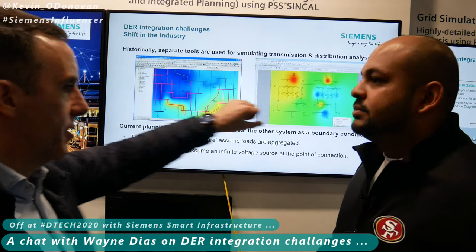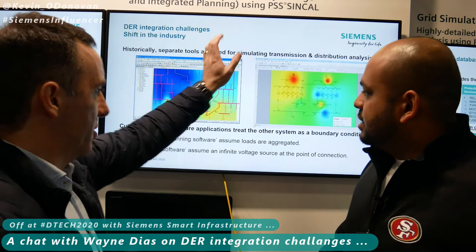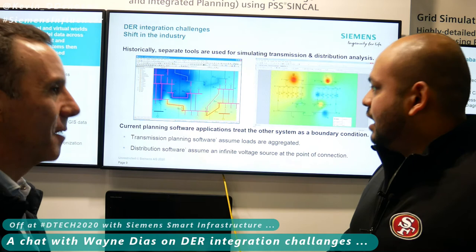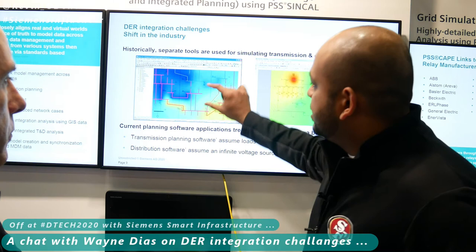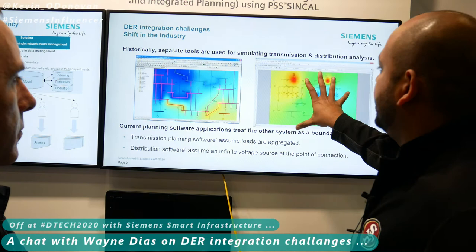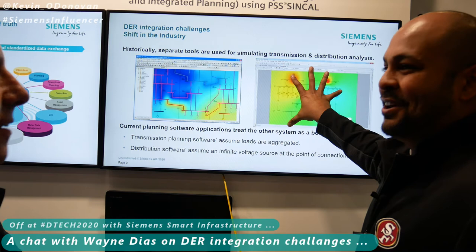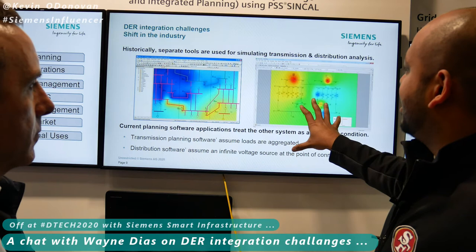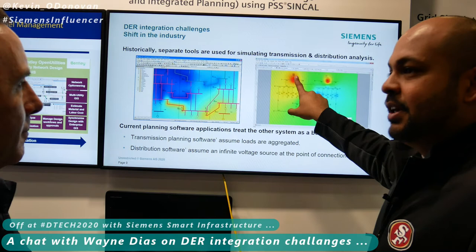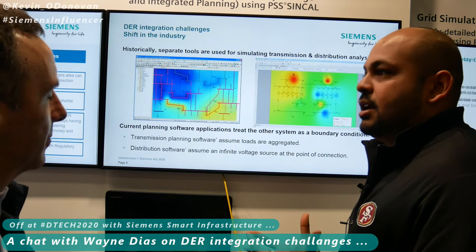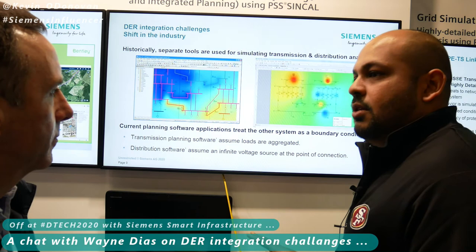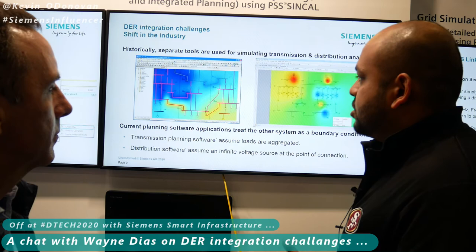What we were chatting about earlier in the week is that there are assumptions made in the models — balanced system, unbalanced system. Currently, TSOs run their analysis by considering the entire distribution feeder as just a little load. And vice versa, on the distribution side, the in-feeder is treated as basically an infinite voltage supply. But what we're doing with SINCAL is trying to get away from those assumptions and reflect the physical aspects of the power system, making sure we're comparing apples to apples.